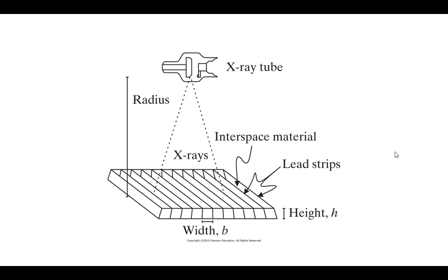So it's really high compared to the associated width that can go through. So you get a very, very narrow angle range, which is the goal, right? We're trying to stop that Compton scattering. That prevents blurring the image. That's the whole reason you do this. The grid is there to prevent blurring. That ratio just tells you what angle theta is going to be permissible. Anything else gets removed. And this is really all due to the Compton scattering. Good?